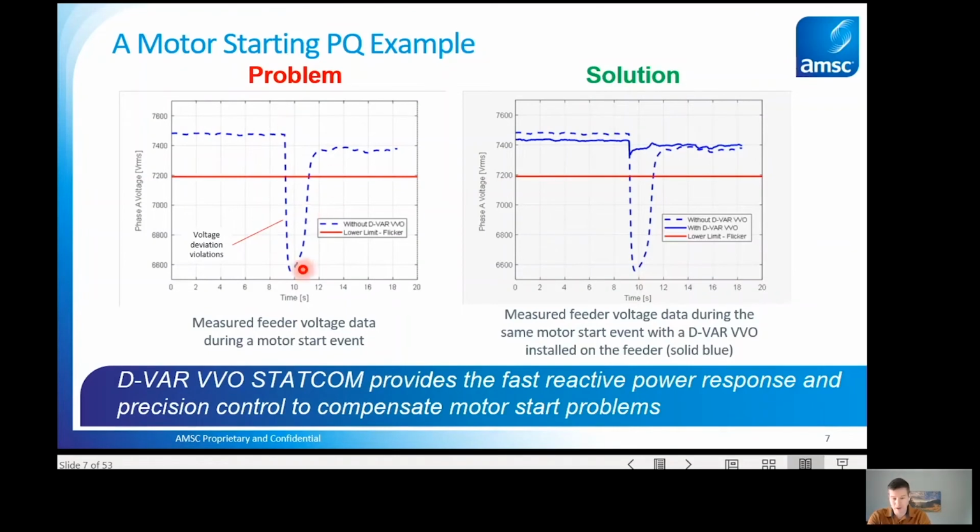Very clearly a power quality violation, not just that facility experiencing low voltage, but dozens of customers on that same utility circuit experiencing that same disruptive voltage dip. So this really is the type of problem that occurs and why it's so disruptive. On the right now, we're emphasizing this concept of being a reactive current problem.